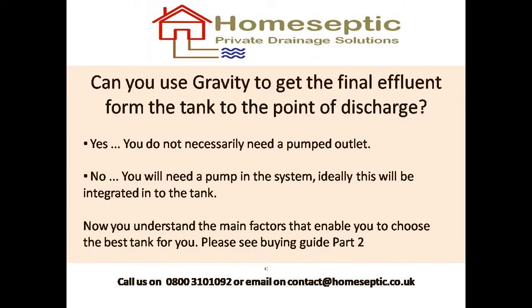Okay, so can you use gravity to get the final effluent from the tank to the point of discharge? So the effluent comes into the tank, it runs downhill into the tank, and then can the effluent run further downhill out of the tank to your discharge area, wherever that may be? If it can't, it needs to be pumped, i.e. the effluent needs to be pumped out of the tank. If it can, that's fine, but you need to work out whether your levels are good enough that you can actually have a gravity tank, or whether, for example, if you want to discharge to an area that's higher than where your tank is, then it's going to have to be pumped.